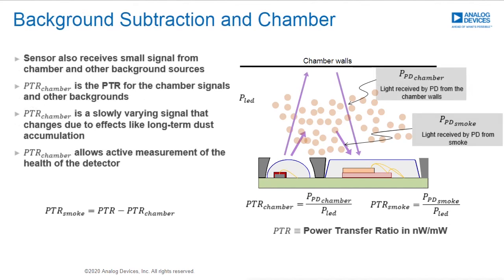So with our device, the optical detection, the scattering of the particles, is performed directly above the module. The LED shines light directly into the space above the module. Smoke particles enter the optical path, and light reflects off of these particles back onto the photodiode. Okay, so when there's a smoke chamber involved, which basically controls the environment around the smoke detection module, you're going to end up with a little bit of background response based on that chamber, because the module is a very sensitive measurement. So anything in the optical path, up to a couple centimeters to a couple inches away, is going to give you some type of background response.